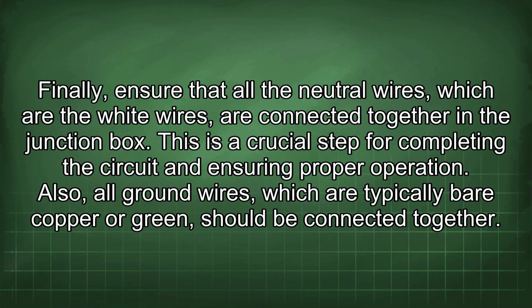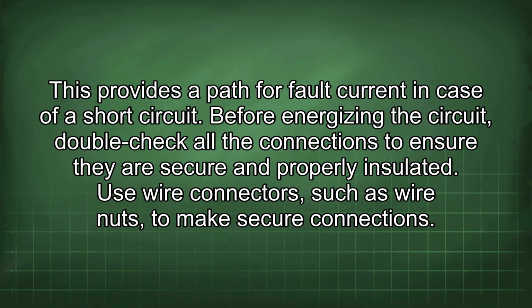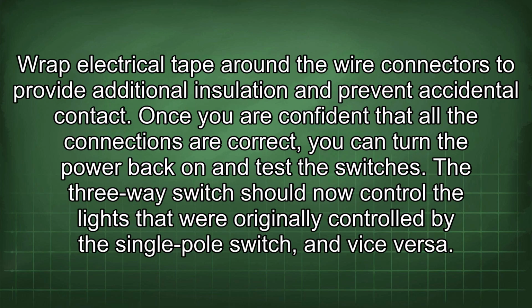Finally, ensure that all the neutral wires, which are the white wires, are connected together in the junction box. This is a crucial step for completing the circuit and ensuring proper operation. Also, all ground wires, which are typically bare copper or green, should be connected together. This provides a path for fault current in case of a short circuit. Before energizing the circuit, double-check all the connections to ensure they are secure and properly insulated. Use wire connectors, such as wire nuts, to make secure connections. Wrap electrical tape around the wire connectors to provide additional insulation and prevent accidental contact.